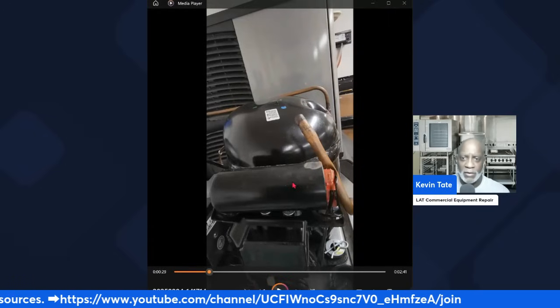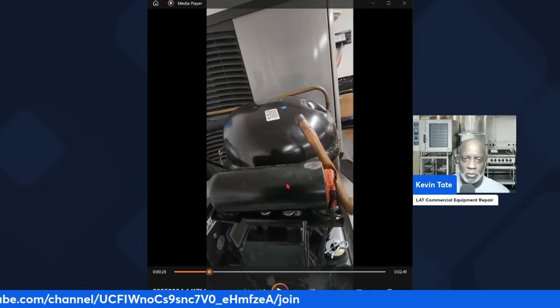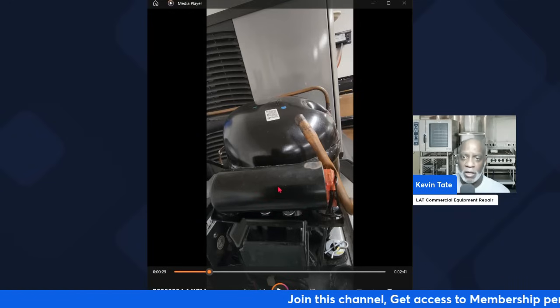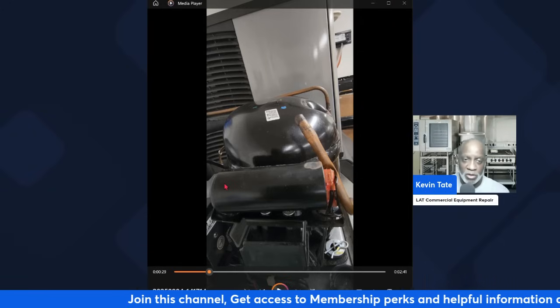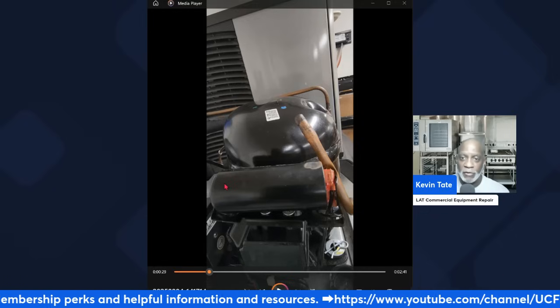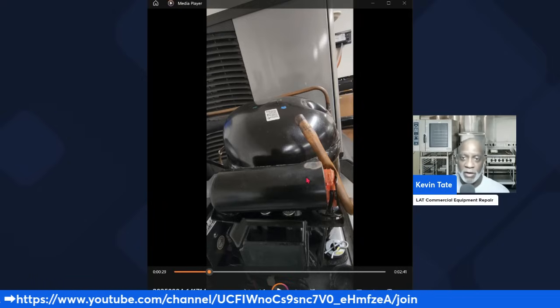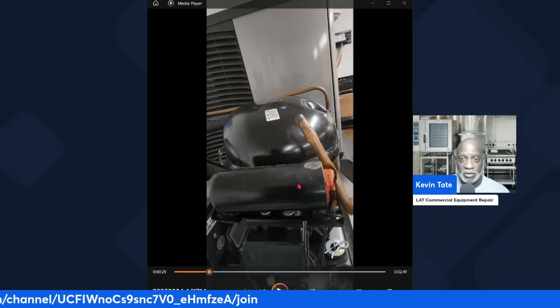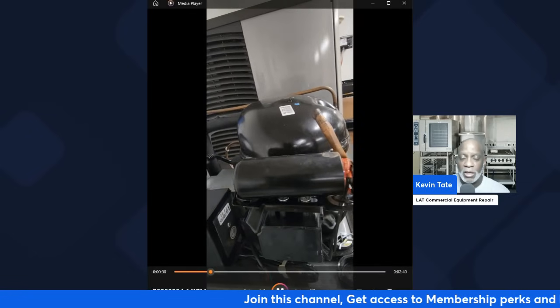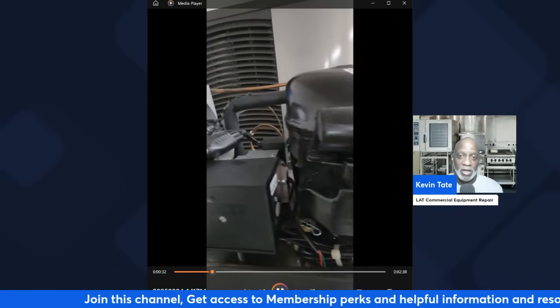It was around 42 to 50 microfarads. So I basically had to consider replacing this capacitor just because of the damage, and because it was lower than the standard manufacturer's reading. I feel better going ahead and replacing that part than just leaving it in there. I left it in temporarily because it was able to get the unit running for now and start cooling, as you'll be able to see in the video. It is running and it is cooling, but I will be going back to replace that capacitor.